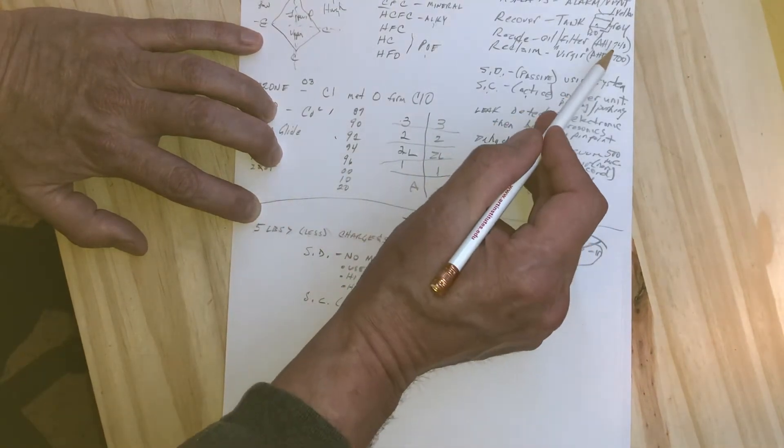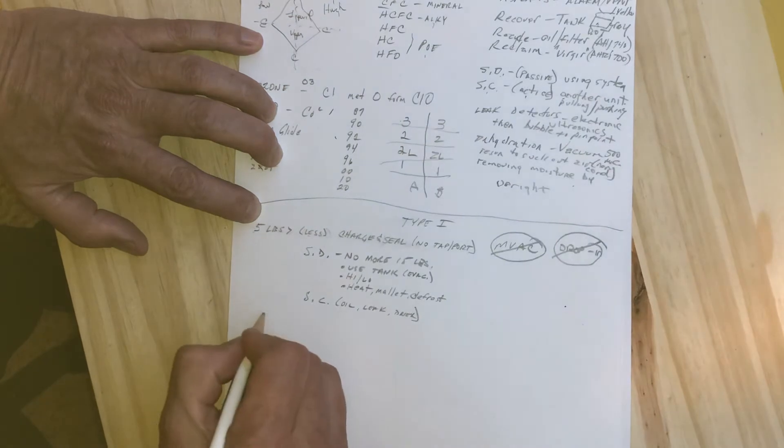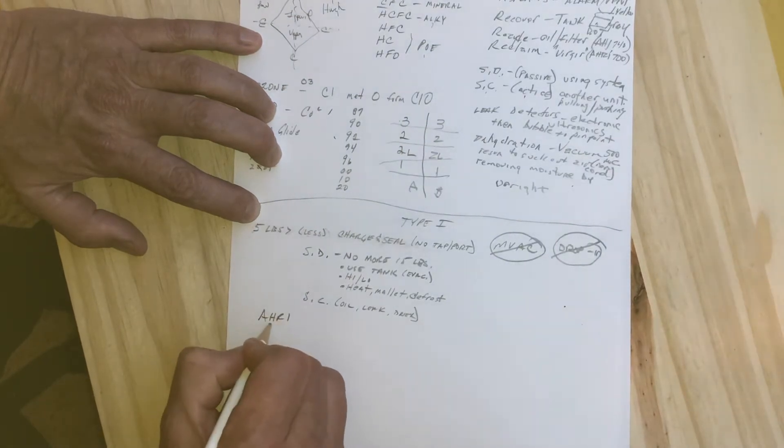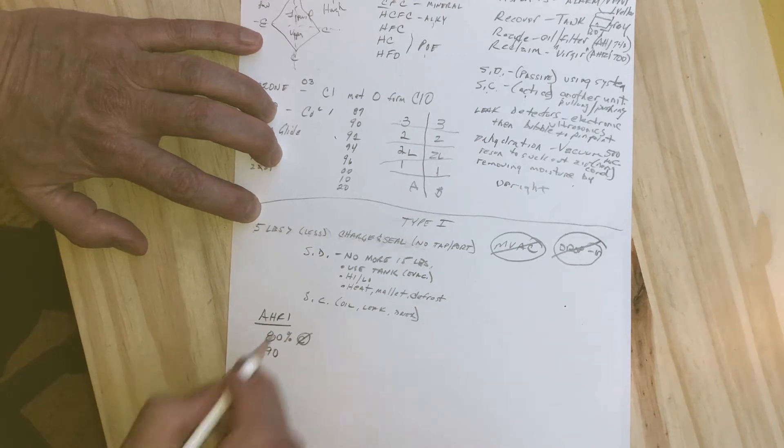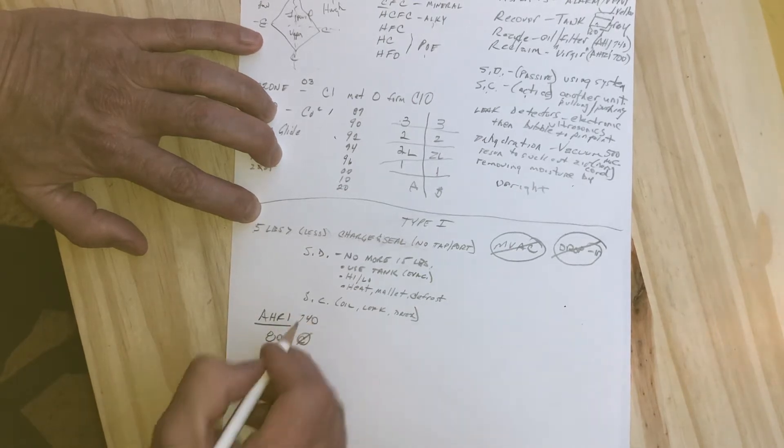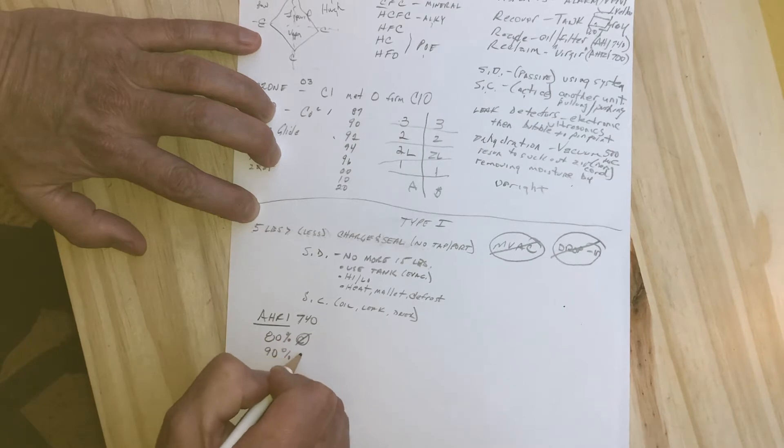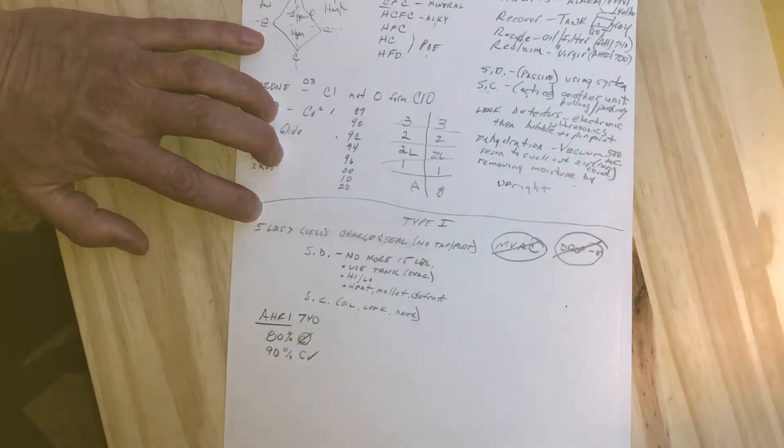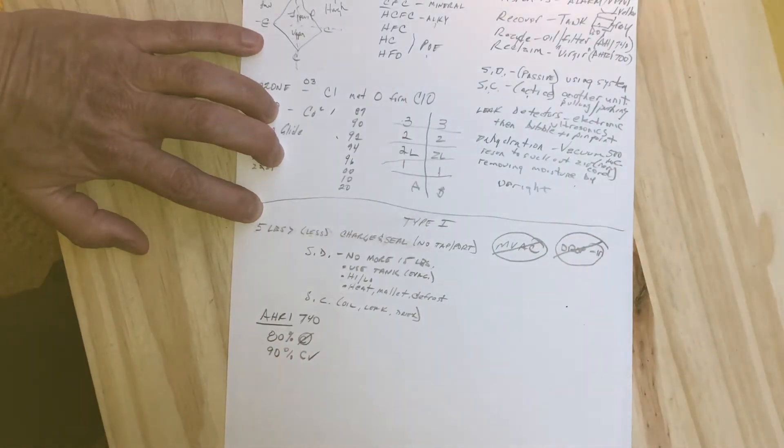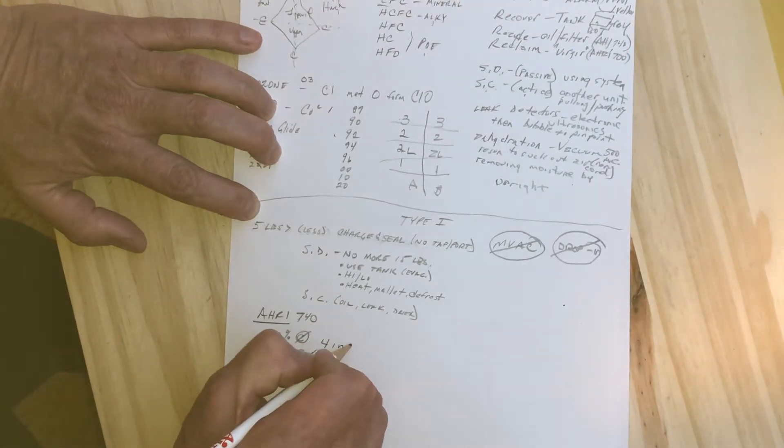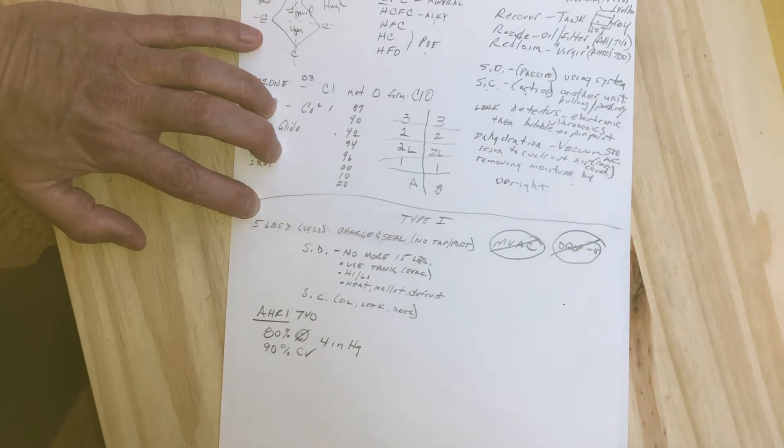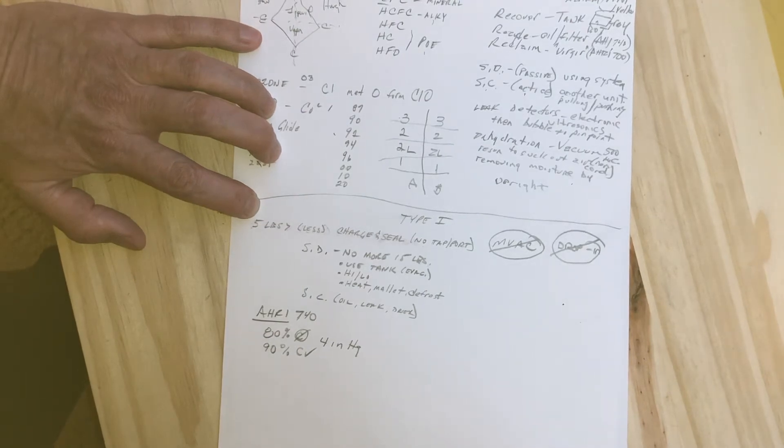Let's talk about AHRI 740. It's an 80-90 rule now, where either the compressor doesn't run and you've got to suck 80% of the refrigerant out, or the compressor does run and checks out and you can get 90% of the refrigerant. As long as we're getting down to a 4-inch mercury vacuum, that's really all they're looking for.